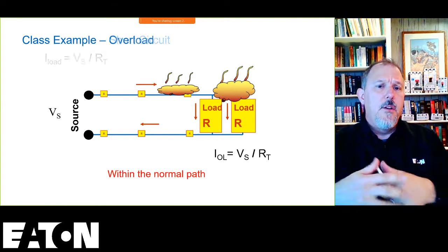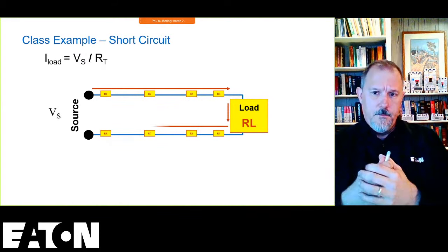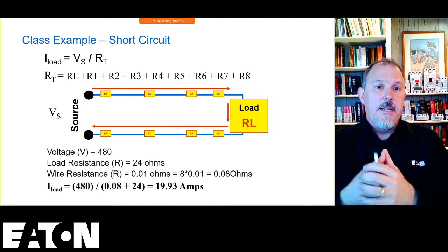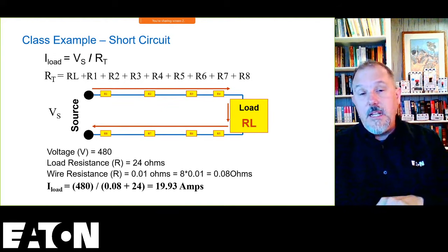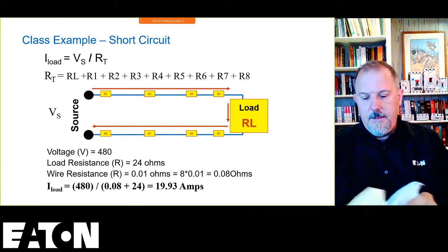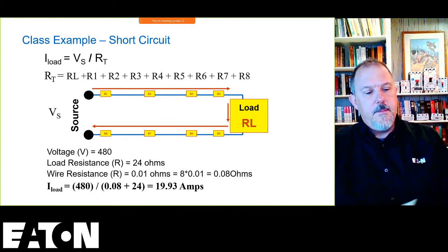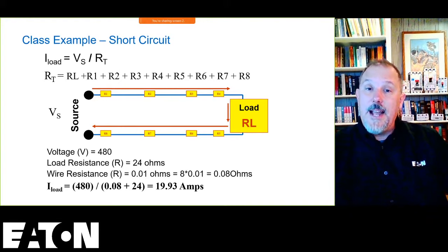So if I look at a normal circuit, each of those resistance values could be your conductors based upon the length and the impedance values found in the table. I think it's Table 9 of the NEC. Let me just double check. I like to make sure that I have the right info. Yes, Table 9 in the National Electrical Code gives us the alternating current resistance and reactances.